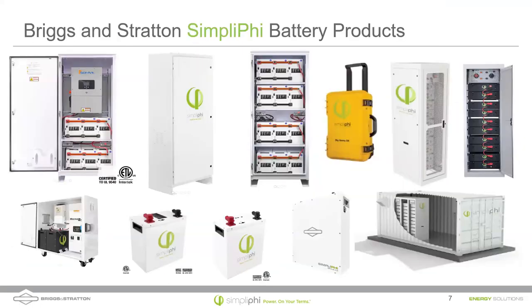Sure. So we do have one question already, from Kenny, and he's asking when will we have our high voltage systems ready? Before I let you answer, I'll just point out on the right-hand side that high voltage stack you're seeing there, each one of those modules is 4.3 kilowatt hours, and they can either be 24 or 48 volts nominal. And unlike some of our access cabinets where all the batteries are in parallel, these batteries are all in series to build up to that high voltage.